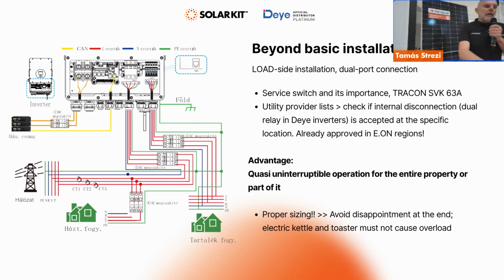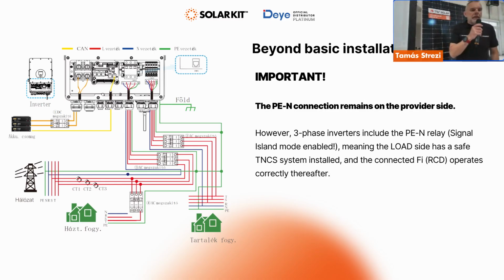One more important thing which Deye doesn't mention: if you use the load connection, it's best practice to add a service switch, where you can switch the load side back to the grid side, whether your inverter is broken or fails one way or another. It's best to have this kind of service switch installed so you can have electricity from the grid as normal. It's specific to Hungary, really, but as generic knowledge it's good to know about.